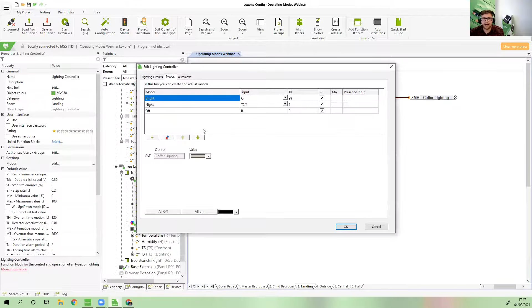That's because it's not designed in the lighting controller. The lighting controller isn't designed to do that. It's very simple to create that logic. You would just take your brightness sensor and put it through a less than block. And every time the value goes less than whatever you want, it would trigger the reset input.